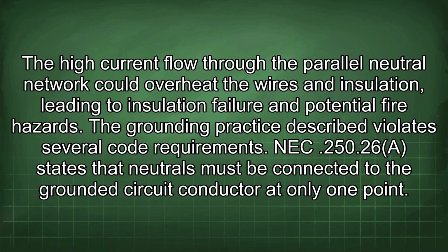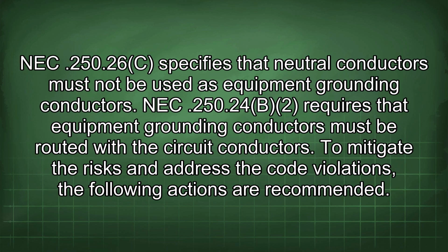NEC 250.26 states that neutrals must be connected to the grounded circuit conductor at only one point. NEC 250.26(c) specifies that neutral conductors must not be used as equipment grounding conductors. NEC 250.24(b)(2) requires that equipment grounding conductors must be routed with the circuit conductors.